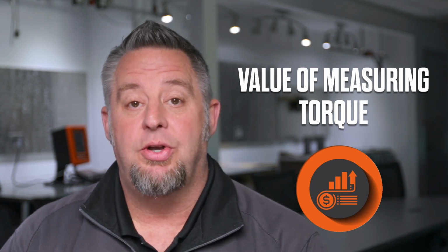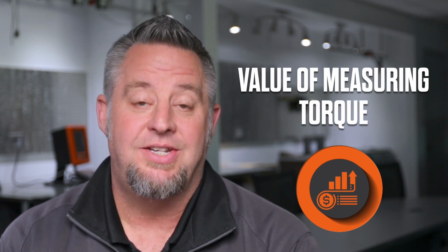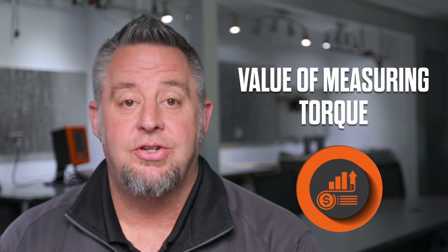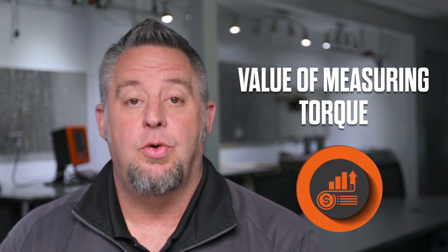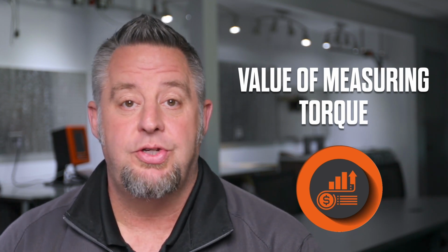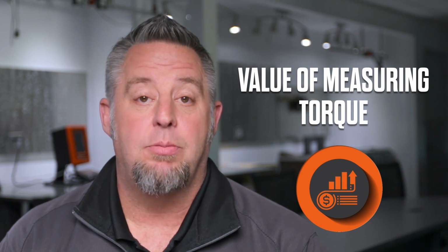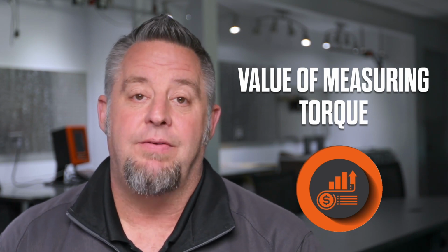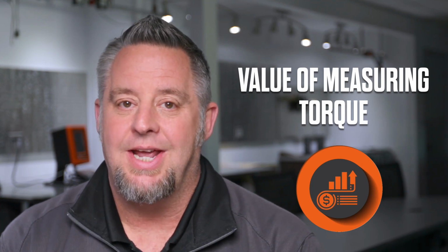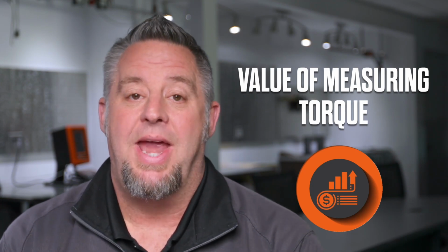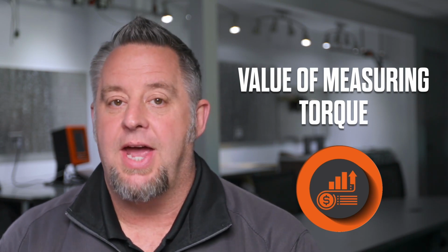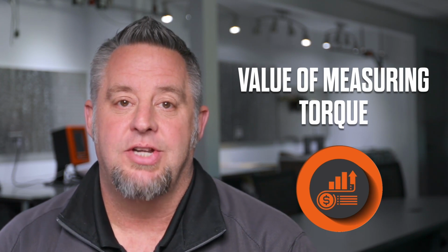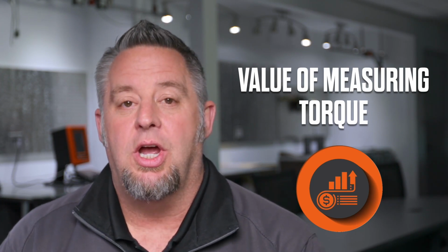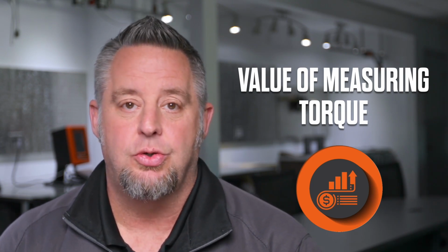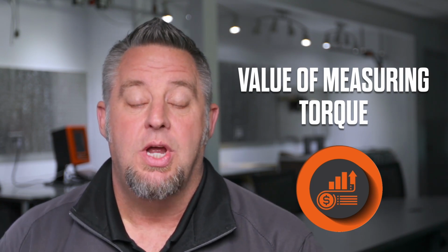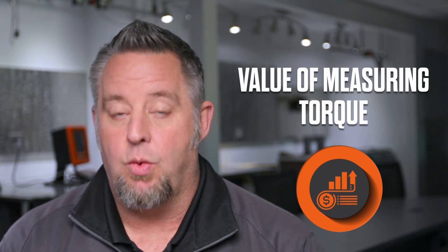We also have the ability to document this type of testing with the use of torque sensors. This can be great to validate and make sure your tools are producing the needed torque in between calibration cycles, giving you documentation and traceability that comes with the sensor. We'll talk more about that when we look at specific sensor types. But there is really good value in being able to go out and test your tools, have the equipment available to find a problem, fix it, and take care of it right away.